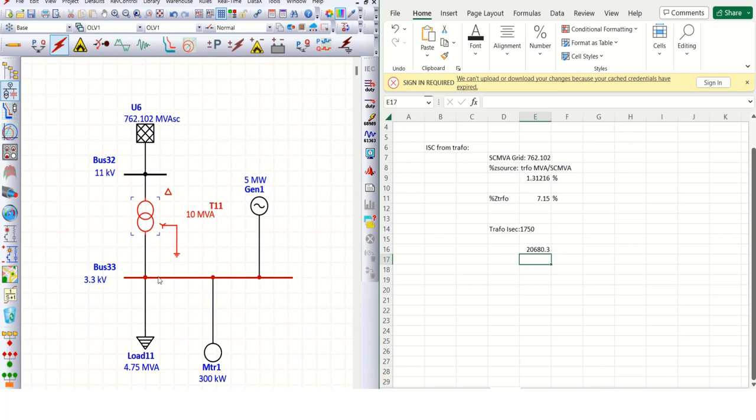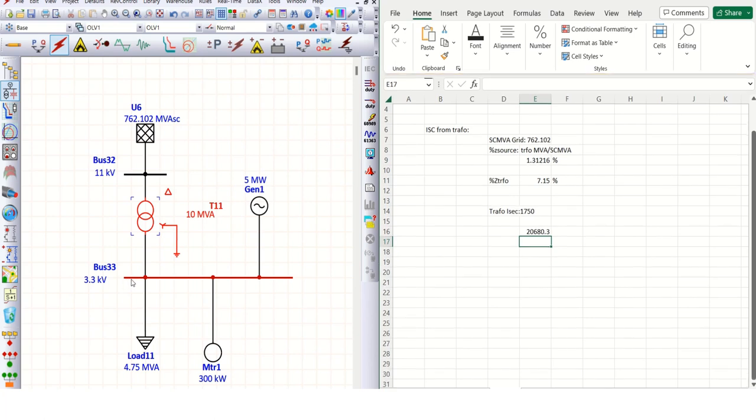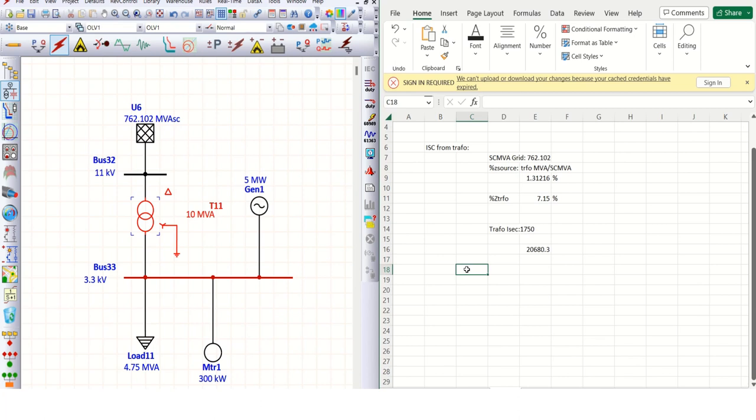But ETAP always gives multiplication with the C factor. For voltage greater than 1 kV, the multiplication factor C is 1.1. So the ETAP value is going to be 1.1 times this number, approximately 22748. But what is the formula for ISC from trafo?